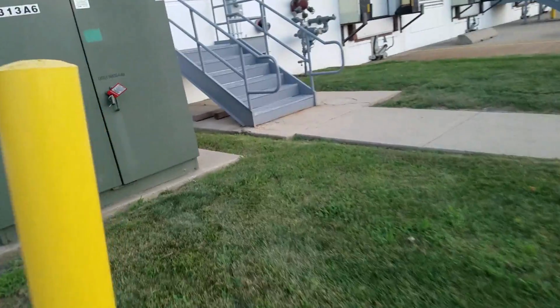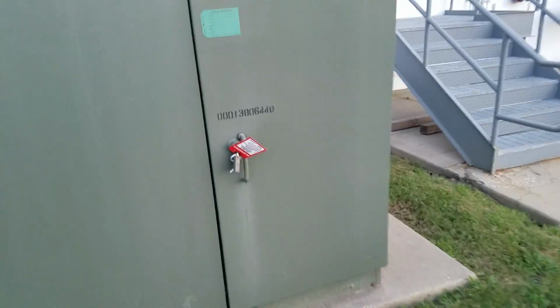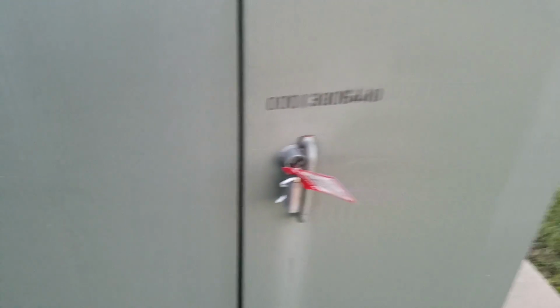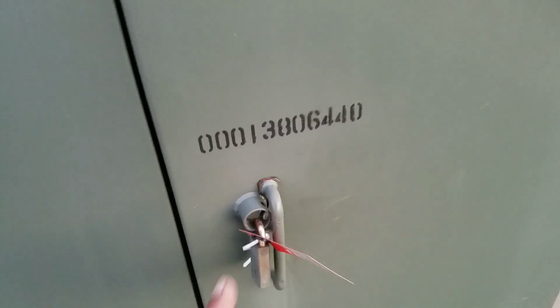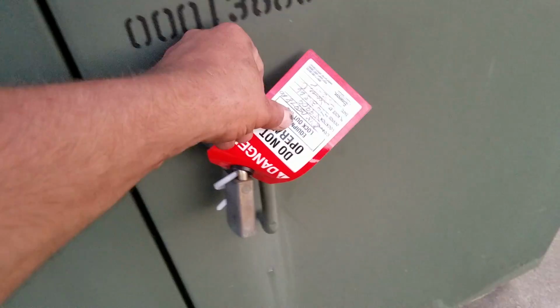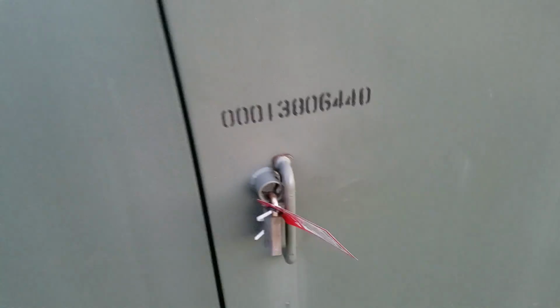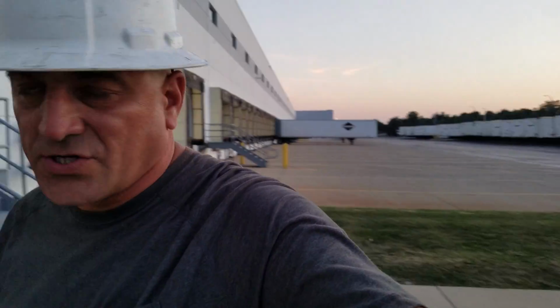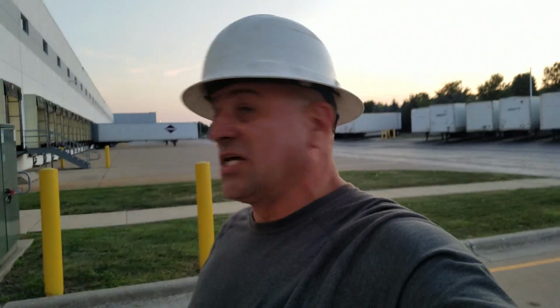Anyway, then tighten all the lugs down to spec, replace covers, and sign off on it. So the power company was already out here. Lockout, tag out, this is locked. This is the transformer. Got 4160 over here, transforms it into 480 right there. Anyway, so there it is. There's a shutdown and startup procedure that you have to follow, and it's not that big of a deal, but it's just procedure, you know. It's what they teach you to do.